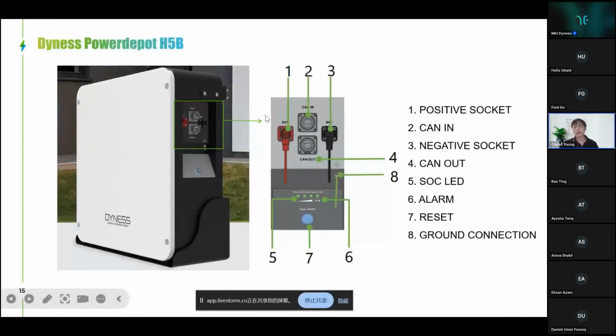The sockets are placed on both sides of the battery shell. On the right is the main interface with the power cable, CAN-in and CAN-out communication ports, SOC and alarm lights, reset button, and ground connection. On the left side is the ground connection and the DC breaker, same as the previous one.